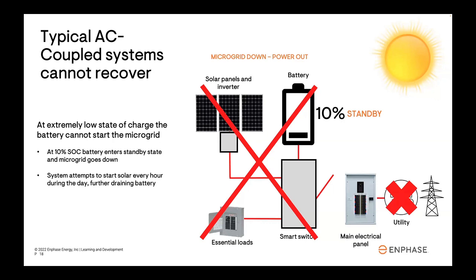During the day, the battery powers up approximately every hour and attempts to start the microgrid and allow the solar inverters to turn on. Every time it does this, it consumes some energy, which can result in the battery dropping down to what's called an ESL, or extremely low state of charge.